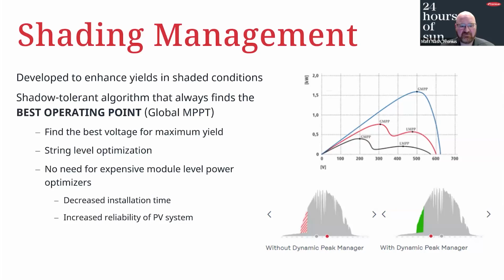One of the key features of the Gen24 is shading management software. It's called Dynamic Peak Manager. So this is a software algorithm that scans the entire IV curve of the strings and then looks for the maximum power output instead of just plotting the highest voltage and then current from there. So it finds the best voltage for maximum yield. It is string level optimization. So it mitigates the need for module level power optimizers, which decreases installation time and improves reliability of the PV system.